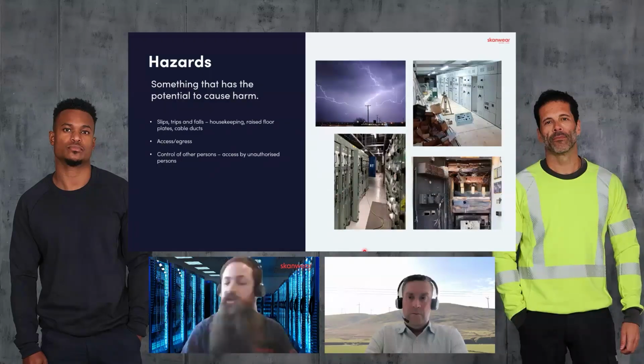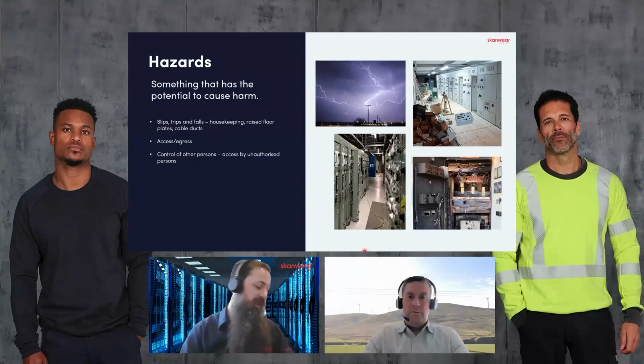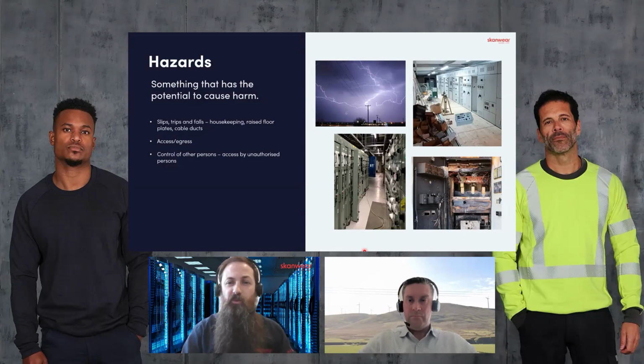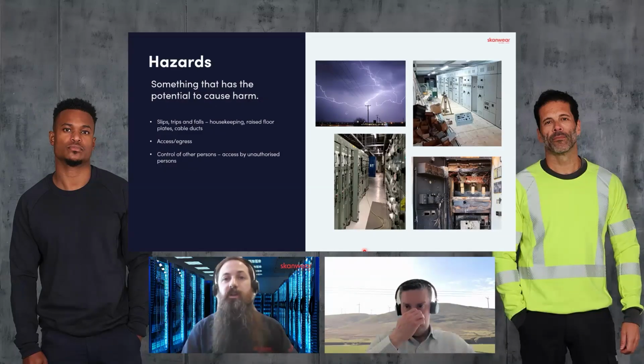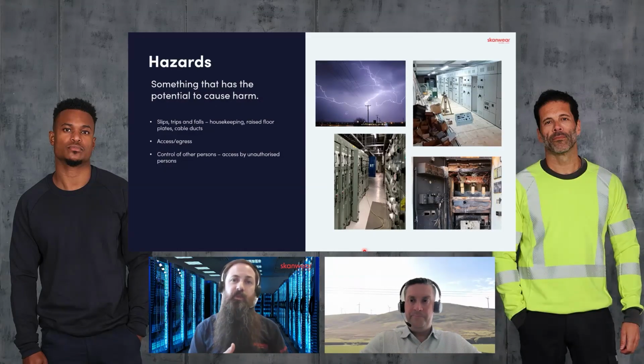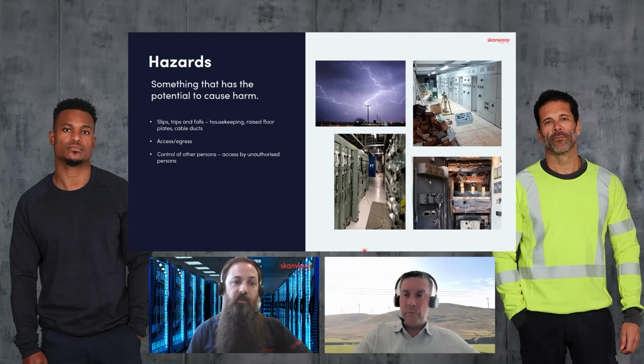And unauthorized persons, again, someone mentioned it earlier around unauthorized access. These are authorized controlled areas because of the risks and hazards that we've mentioned already. If the door is open, people don't tend to go in there with malicious intent. People are curious by nature. So if there's a door open that's not normally open, people do tend to go in there. We've had so many cases where people have gone in and accidentally hit an e-stop and tripped something that's been under high load. Or cleaners: a cleaner won't go in there with malicious intent. They might think, I've never cleaned in there before, I'll go and give it a wipe over. That's where we've had issues in the past, where unauthorized persons have accessed them to try and do the right thing, and they've actually introduced a massive hazard into the compartment. So room integrity and control of the doors is massively important.